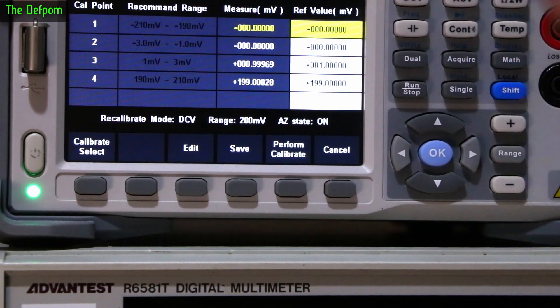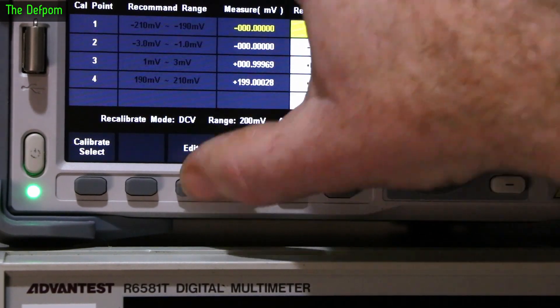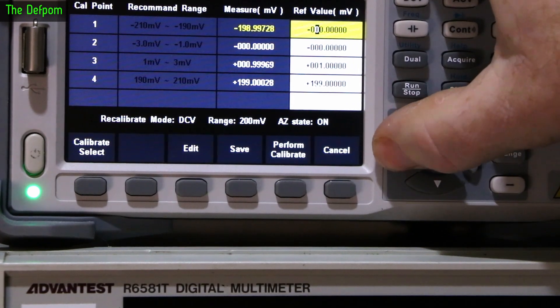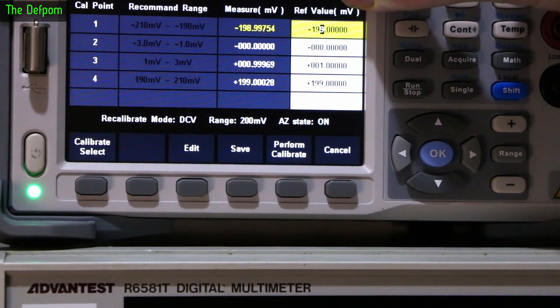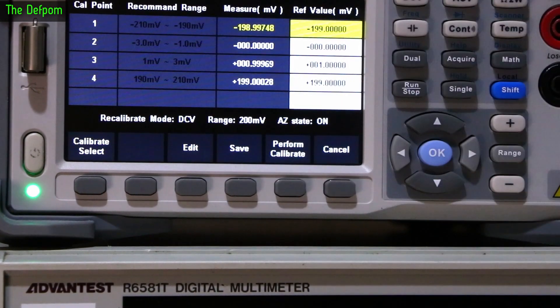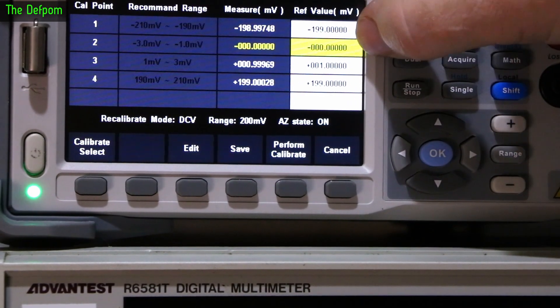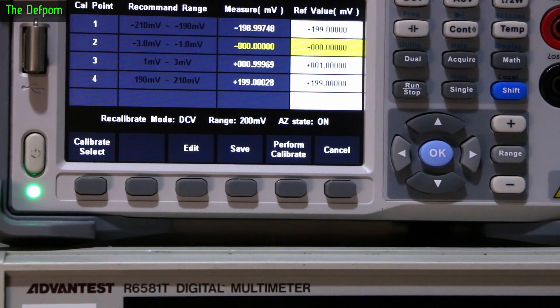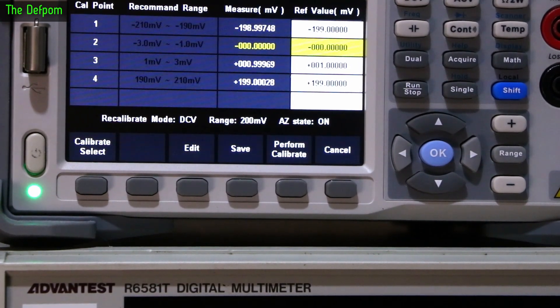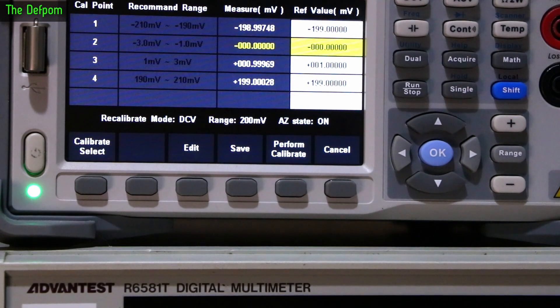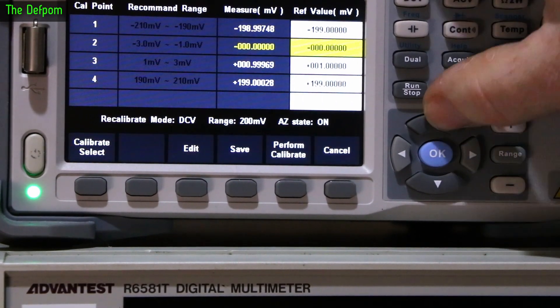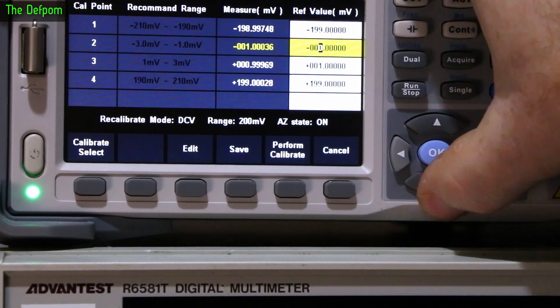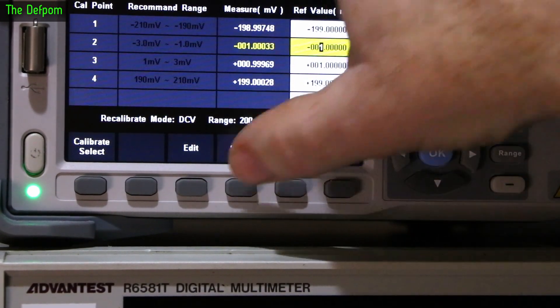We'll come down and do the other end of the scale. It's still stabilized. We can do negative 200. That's minus 199, exactly what we've got on the Advantest. Save that one. Then we'll do the minus one millivolt range. Every time I change the setting on the calibrator, I need to give it a chance to stabilize. Things have to reach an equilibrium. That's now doing minus one millivolt exactly. So we can adjust that one. Save.